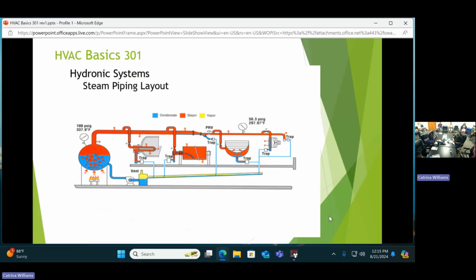So as that steam goes through that unit heater and through that coil, and we're blowing cold air across that coil, that steam begins to change states again from a vapor back to a fluid. We call that condensate. So the whole purpose of all these traps, did somebody have a question? The purpose of all of these traps on each one of these devices is to trap the steam and keep it out of the condensate piping and allow water to flow. And as that changes states within that coil, it can actually go from say 15 psi steam all the way into a negative. And we want to break that vacuum as we go through there.